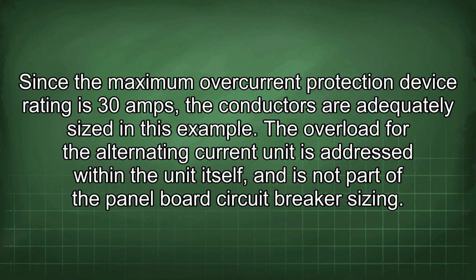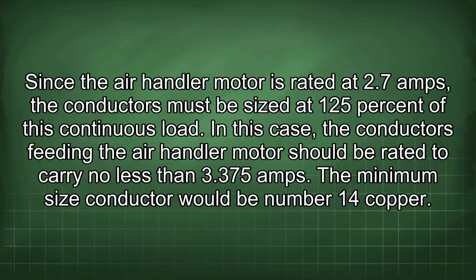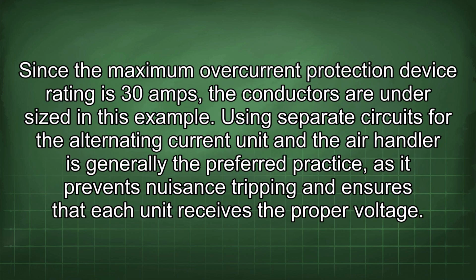Since the maximum overcurrent protection device rating is 30 amps, the conductors are adequately sized in this example. The overload for the alternating current unit is addressed within the unit itself, and is not part of the panelboard circuit breaker sizing. Since the air handler motor is rated at 2.7 amps, the conductors must be sized at 125% of this continuous load. In this case, the conductors feeding the air handler motor should be rated to carry no less than 3.375 amps. The minimum size conductor would be number 14 copper. Since the maximum overcurrent protection device rating is 30 amps, the conductors are undersized in this example.